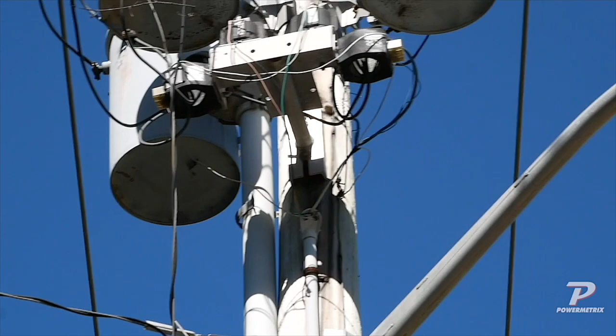If you pick it up over on the right side, we've got our 480 coming in, and it is looped through that right CT. So the 480 is looped through the right CT, and on the left CT, on the left side of the bracket, we've crisscrossed A and B phases on the 240 side.